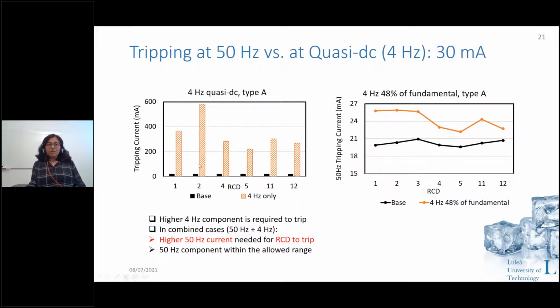For the quasi-DC component, we tested with 4 hertz. And in case of type A RCDs, this is where pure quasi-DC 4 hertz components, and this is what was fundamental. But with pure tones, it requires really high currents, like 400 milliamps, 600 milliamps for it to trip. Although it trips, it's very high. And with a combination of currents where the 4 hertz component was 48% of fundamental, all the RCDs tripped at a lower value. So a lower fundamental current is required for them to trip. So even 4 hertz basically helps type A RCDs to trip.